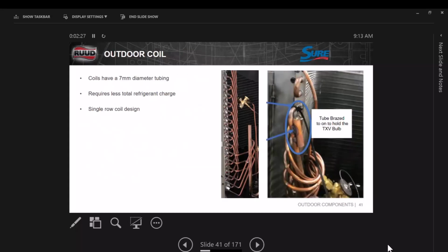You'll see these little tubes brazed onto the end of the coil. That's where the thermistor slides into. So you'll see this little brass or stainless steel clip that holds the sensor, and it pushes it up against the line inside. So we have a good thermal sensing device right there. So that is the tube for the sensor for the expansion valve, and any thermistors that you see throughout the system are going to be in this.